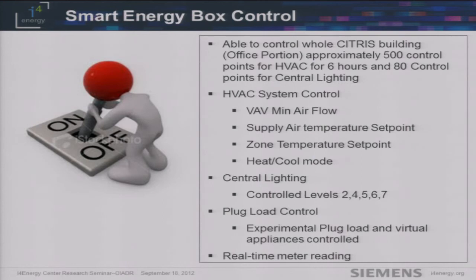The Smart Energy Box was able to control in the Citris building approximately 500 points for HVAC, for the 6 hours we did, and 80 control points for the lighting system. In the HVAC control, it involved VAV minimum airflow, supply air temperature set point, zone temperature set point, and also heating/cooling mode, because we have to force it into the cooling mode when we pre-cool the building. And also central lighting, where we control 5 levels in this building, and plug load control, and we were reading the real-time meter data as well.